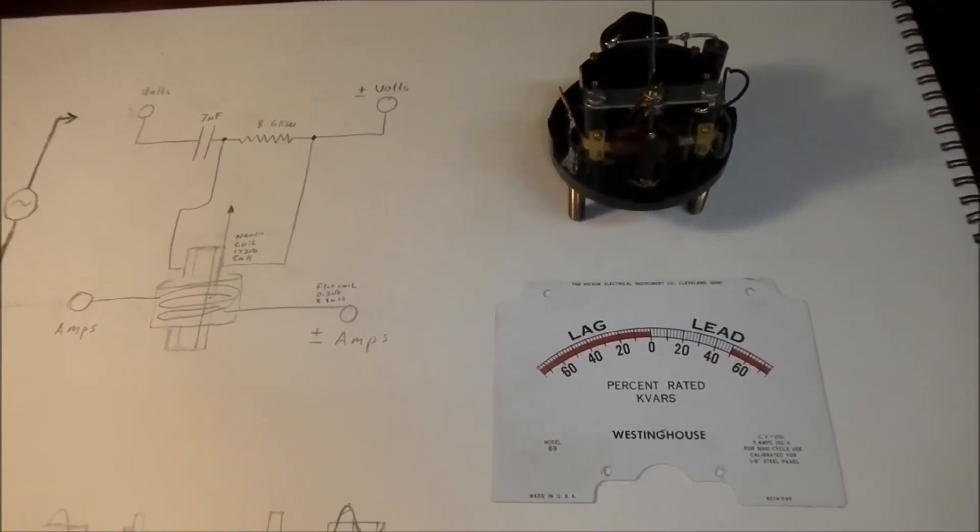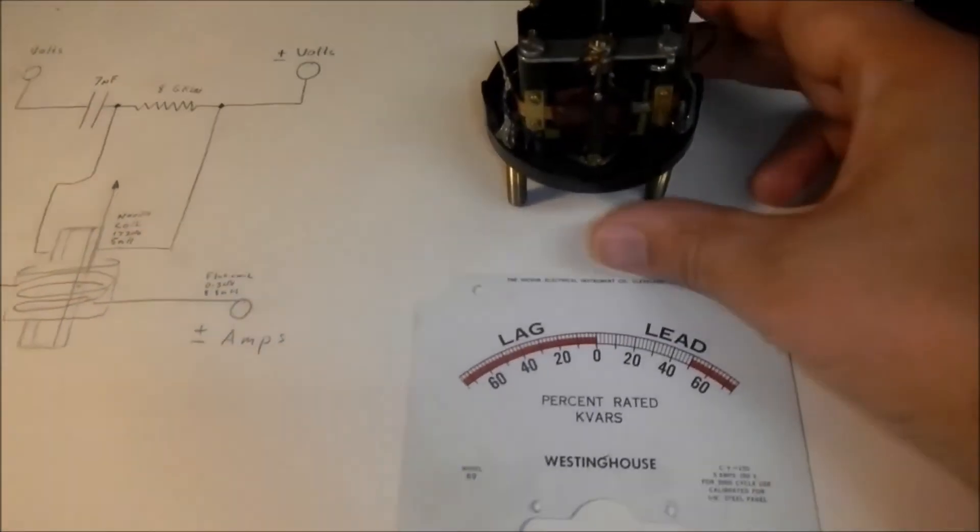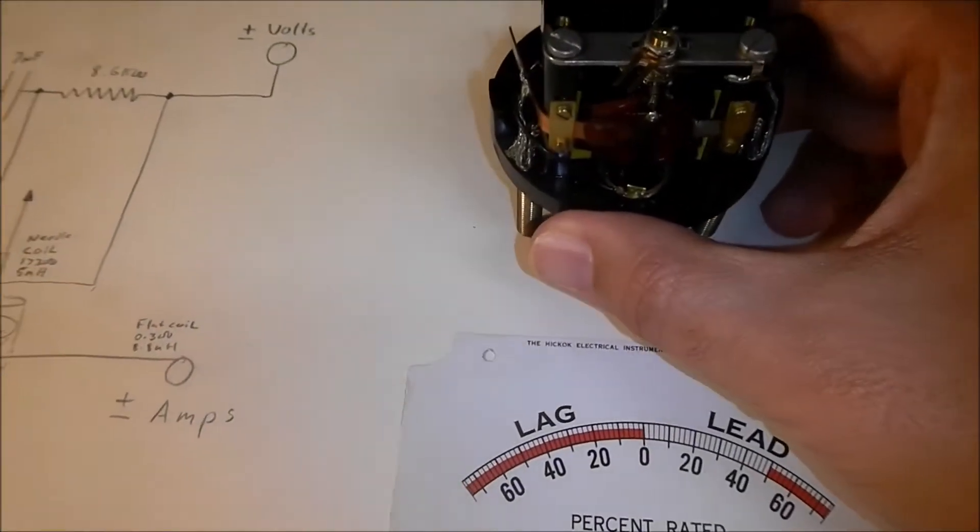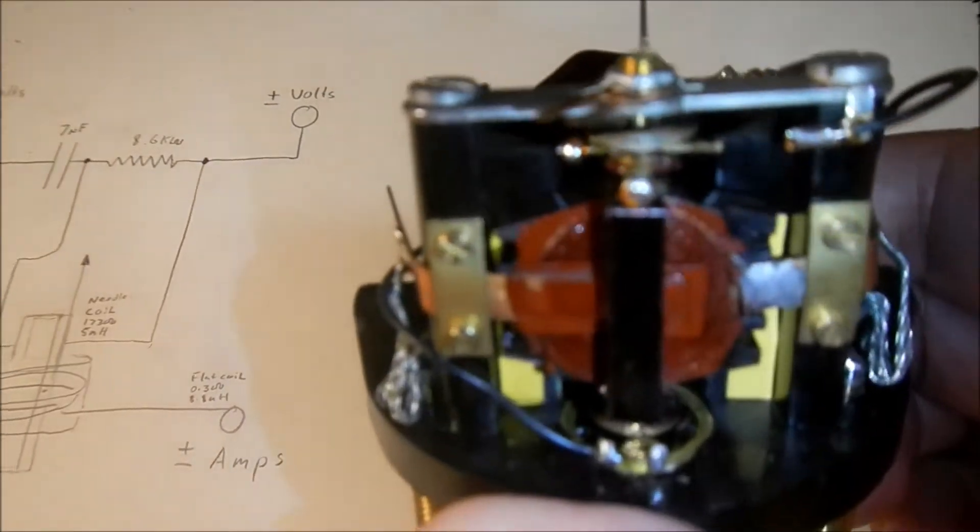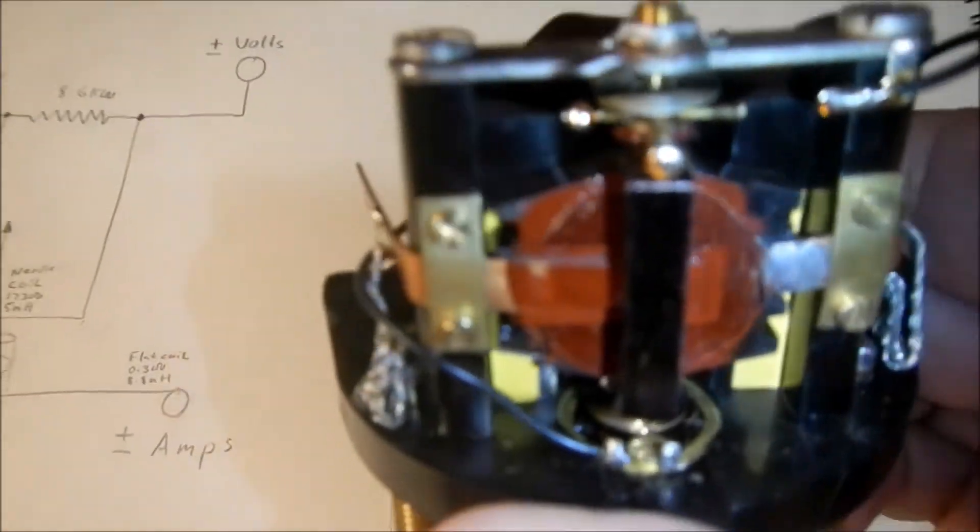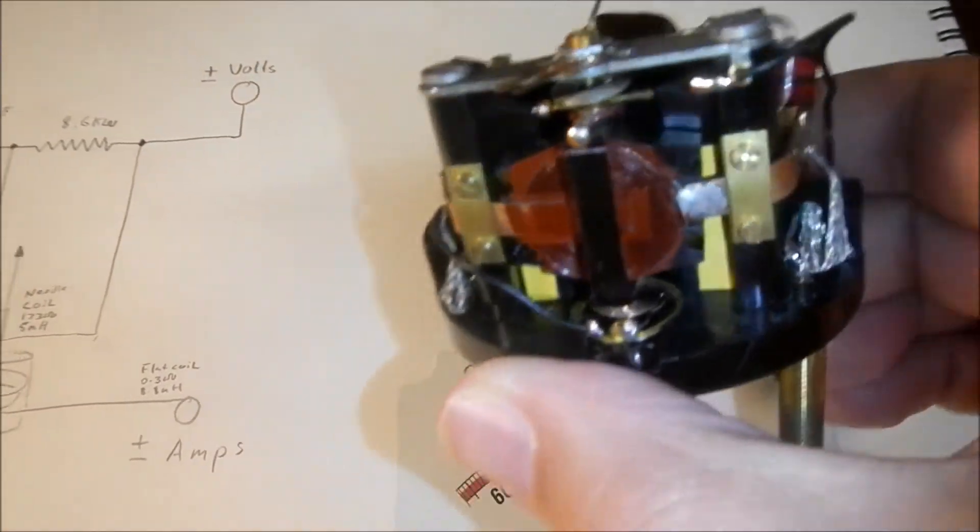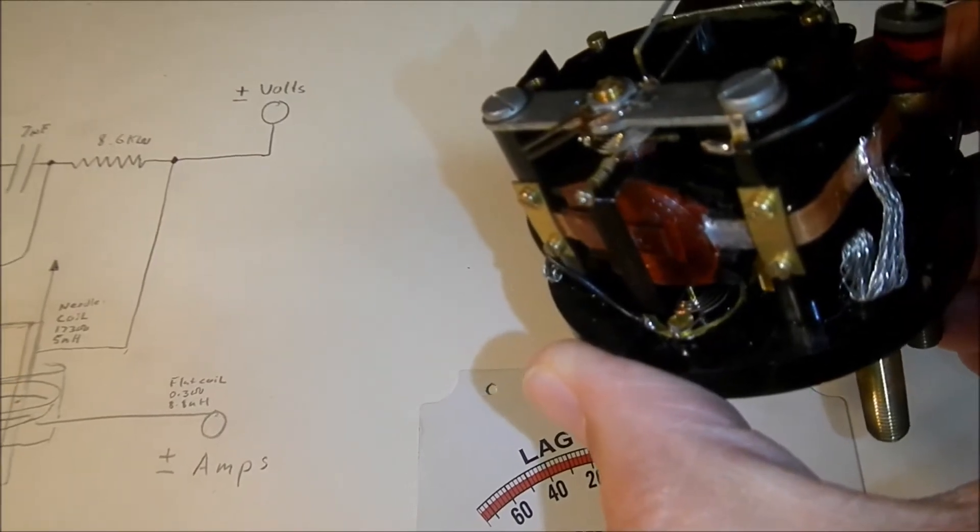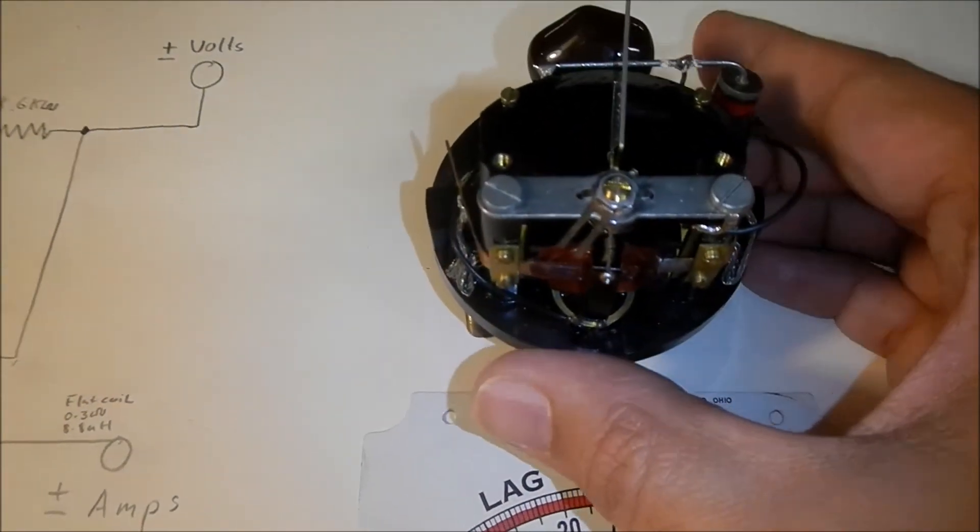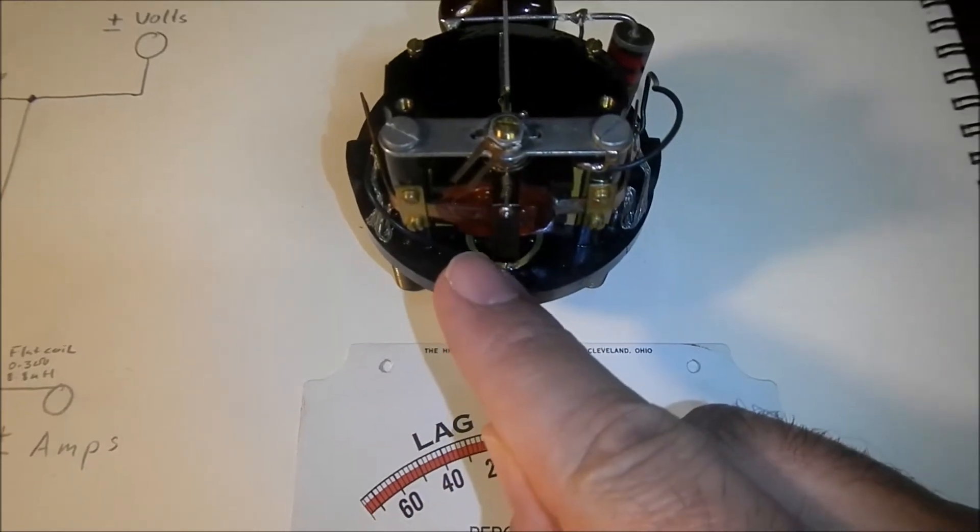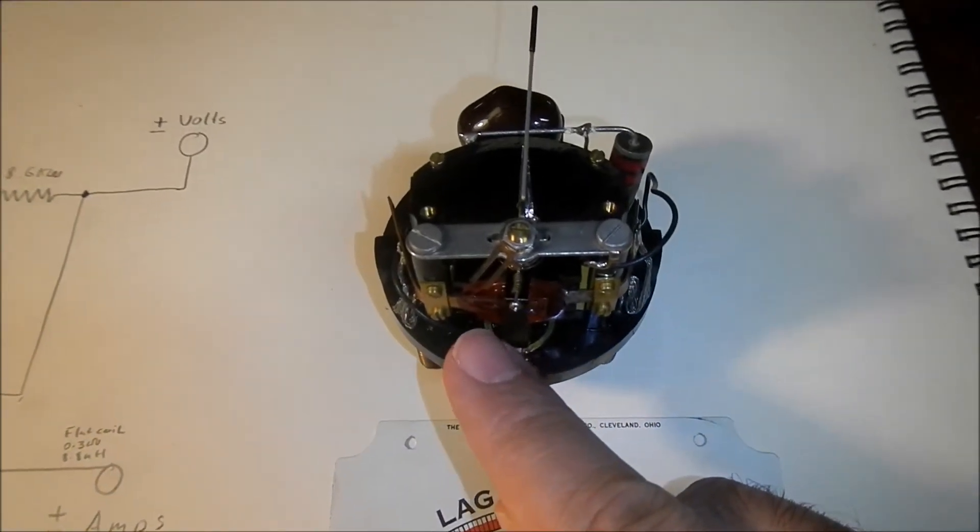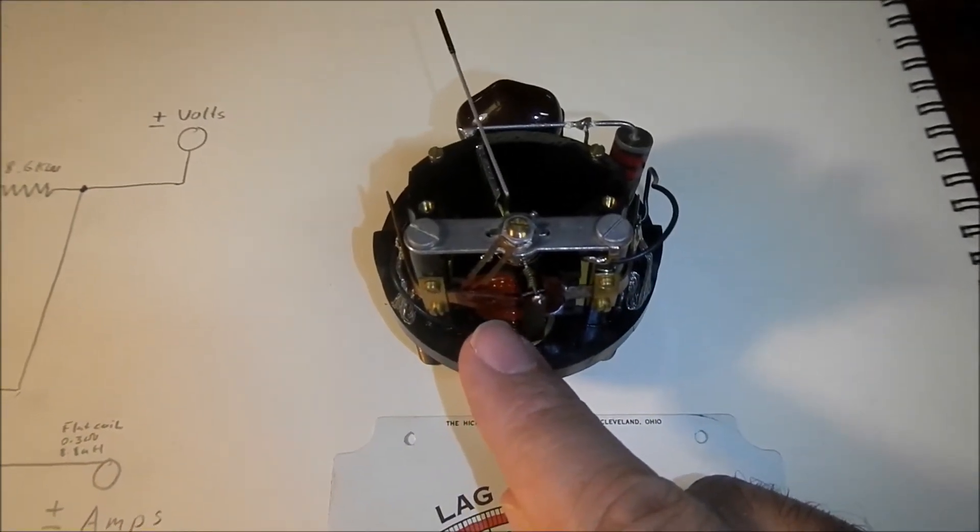But it's kind of neat, it's an analog power factor meter and what it has is two coils perpendicular to each other. And when the current in one coil becomes out of phase with the current in the other coil, it will deflect the meter.